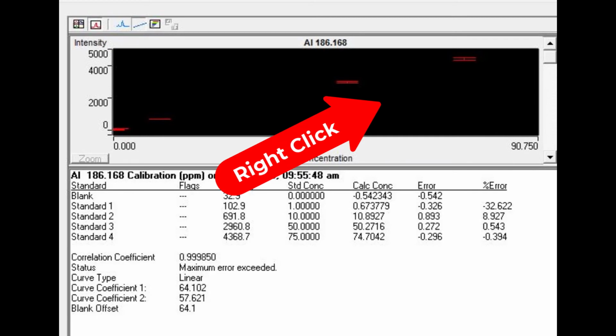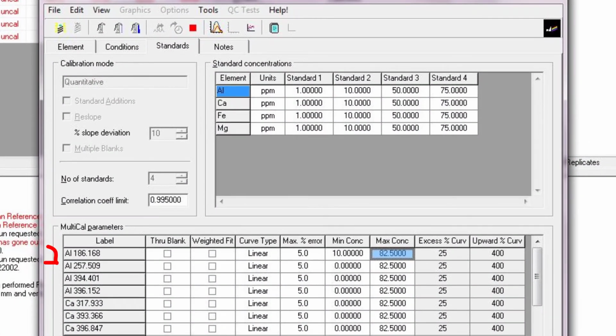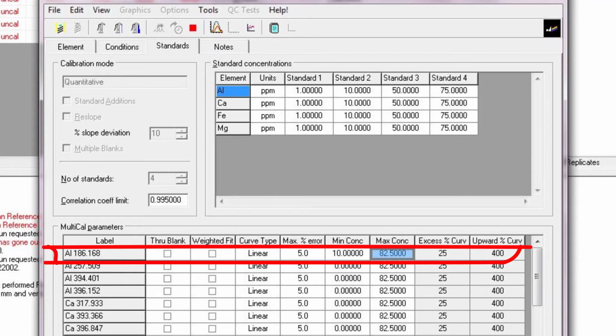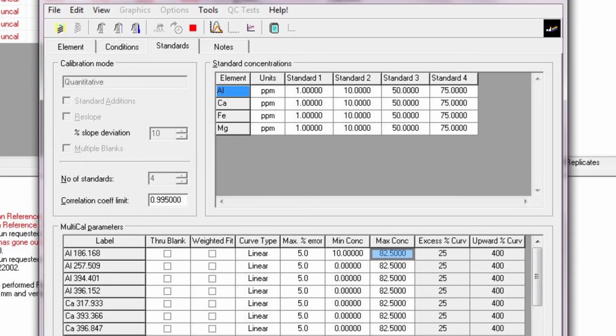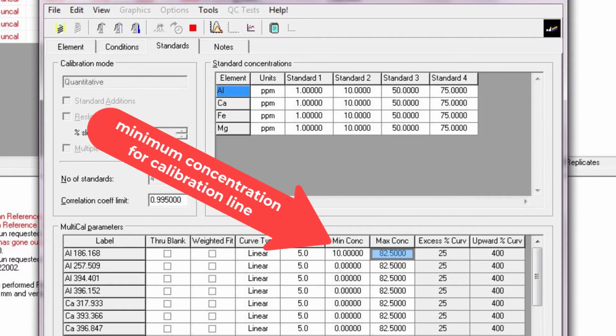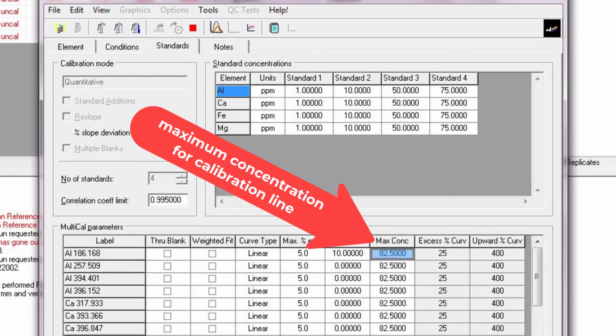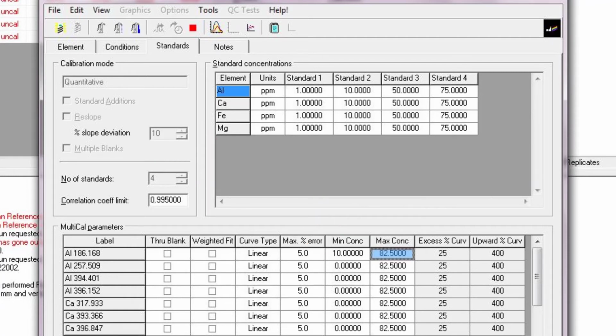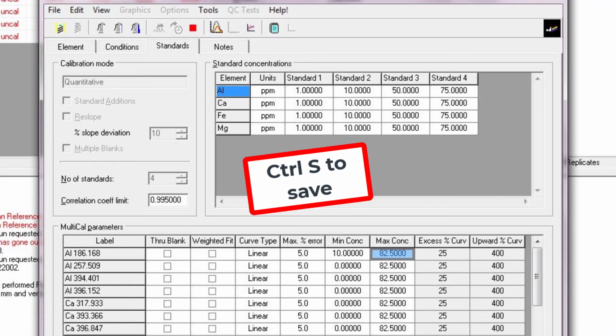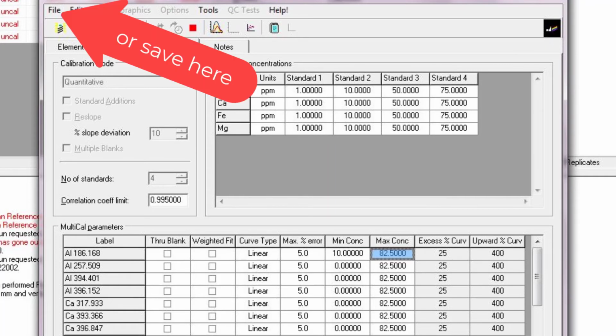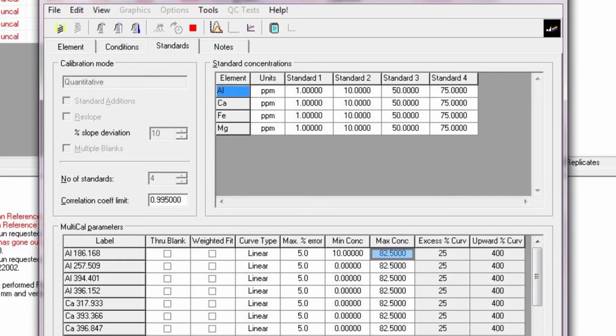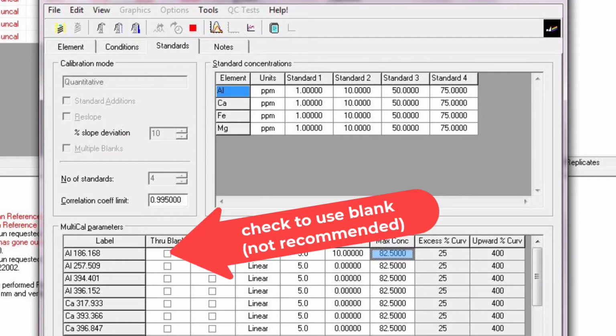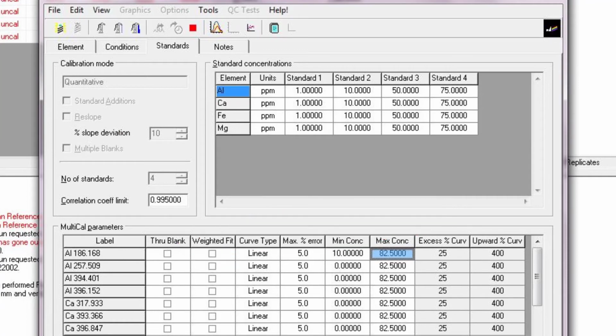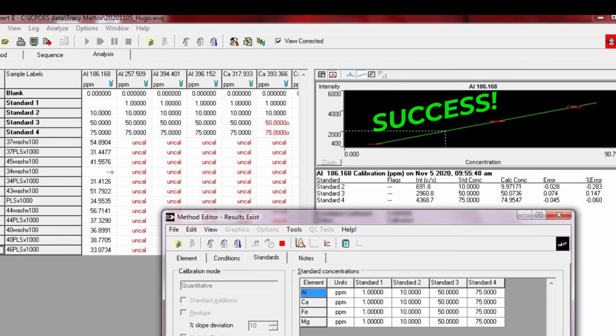Right-click on the black portion of the screen to enter the method editor. The aluminum 186 wavelength is the first line. Since I expect the actual concentration of my samples to be close to 40 ppm, we can omit the 1 ppm standard. To do this, I insert 10 as the minimum concentration and leave the maximum alone at 82.5 ppm. To save, I can press Ctrl S on the keyboard or use the pull-down under File to press Save. I have the option to increase the maximum error percent or to force the calibration through the blank by checking this box, but in this case, removing the lowest standard should be enough.